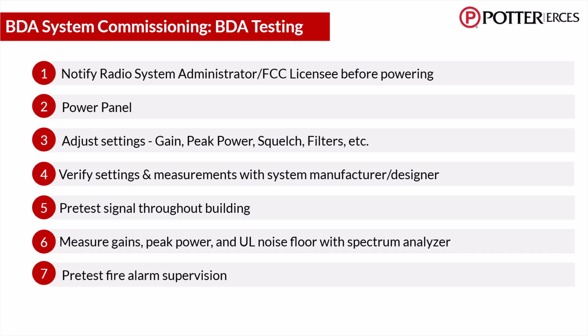You can use the BDA's graphic user interface, called Sentry, to see the incoming and outgoing signal strength. Once you see that the BDA is configured properly, you can conduct your final grid test and test your alarms while the ERCES is operating.